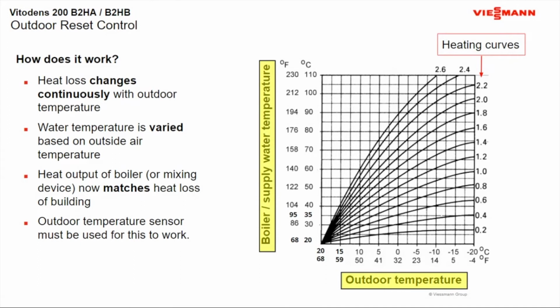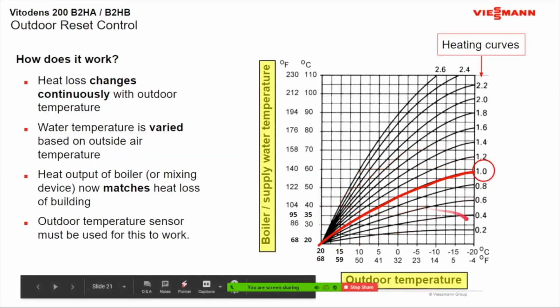So for an example, just to show you how heating curves work and how our heating curves work, we're going to do a 1.0 heating curve today. So what does a 1.0 heating curve mean? On our boiler, it means that when the temperature drops 1 degree outside, our boiler water temperature will come up 1 degree. If you had a 2.0 heating curve, 1 degree drop outside, our boiler water temperature comes up 2 degrees. So each time it drops, our boiler modulates up and down that way. But you're also going to modulate up and down the scale according to the outdoor temperature.